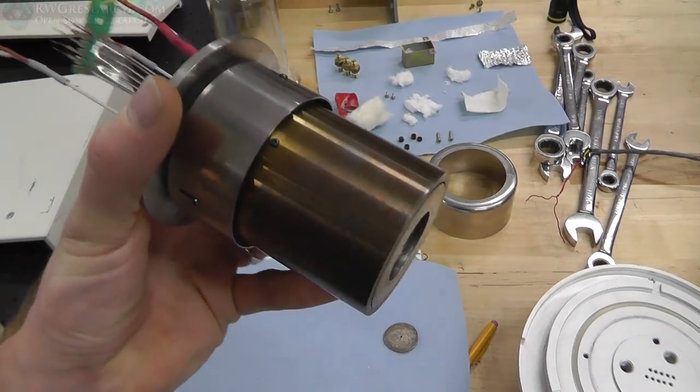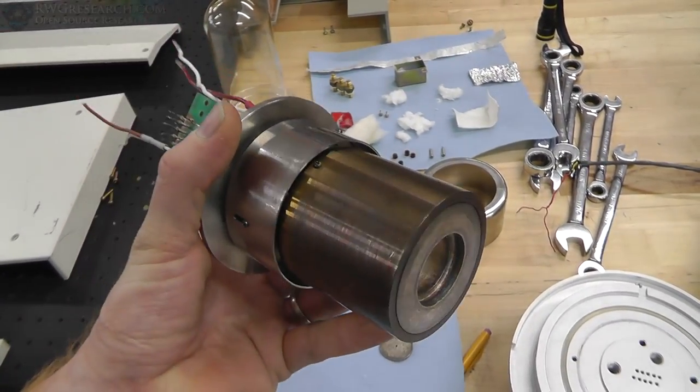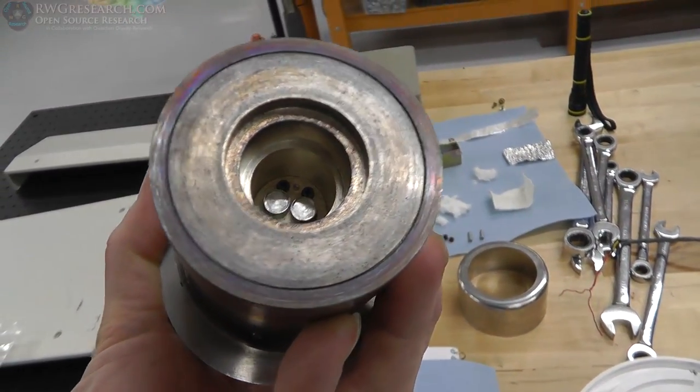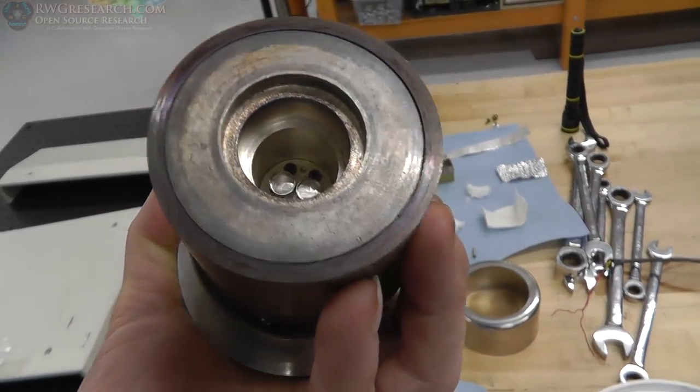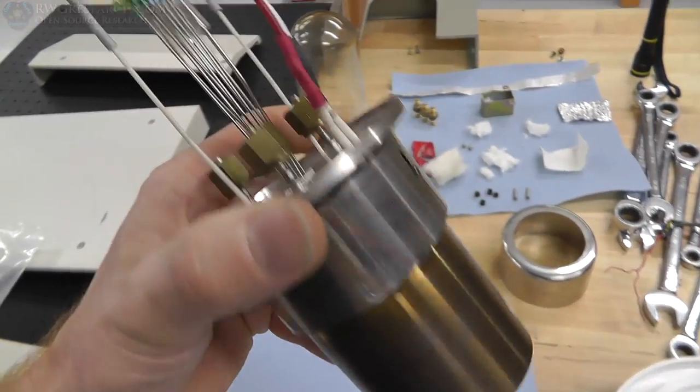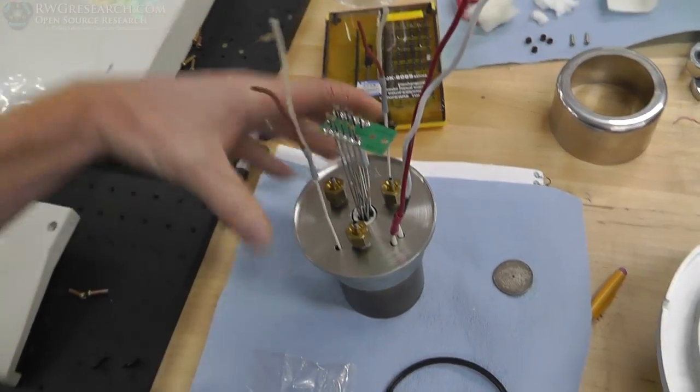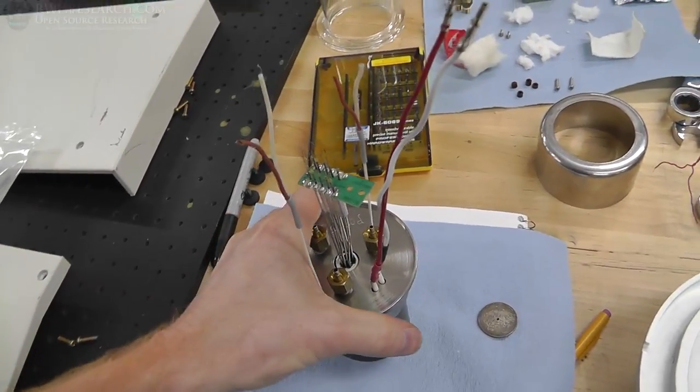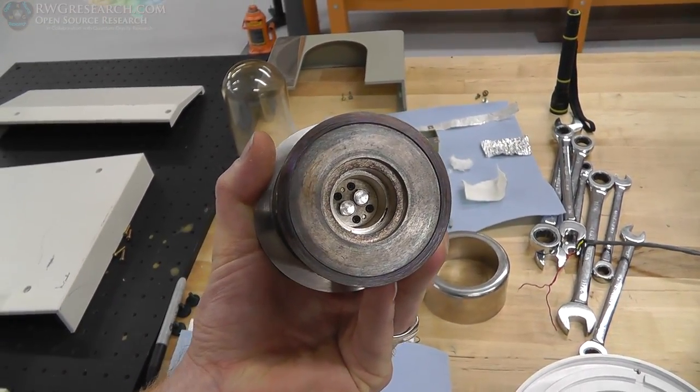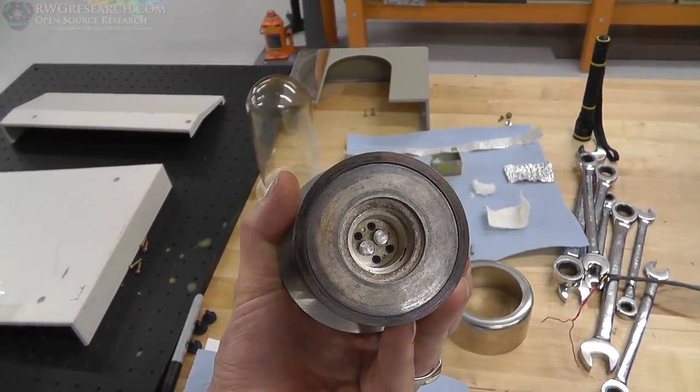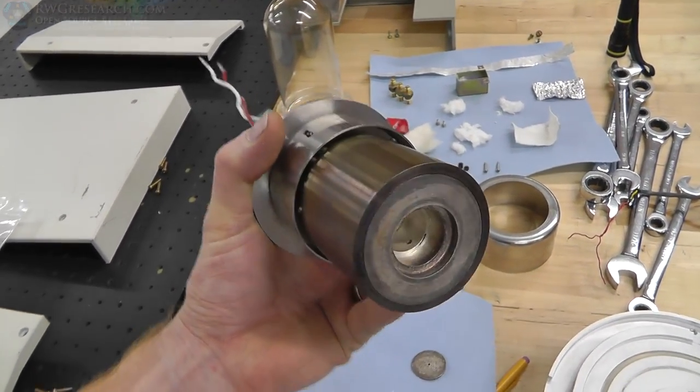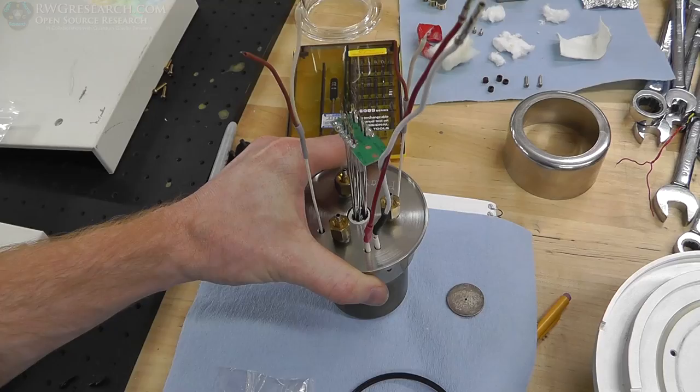This element around here, this big giant block that looks all discolored, that's stainless steel. And I believe that right there is actually silver. So this whole thing is made of silver. And right inside here, there's a heating element. That's these two heavy duty wires that come out of here. So you heat the sample very slowly and you determine when its phase changes are. It'll give off an exothermic or endothermic peak.